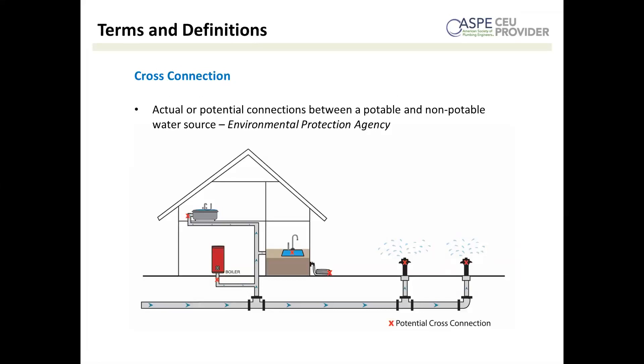A cross-connection, as defined by the EPA, is any actual or potential connection between the public water supply and a source of contamination or pollution. These cross-connections can jeopardize the cleanliness and potability of the public water system in a backflow or back siphonage event. An actual connection is a direct connection to a source of contamination — for example, a boiler feed water makeup line connected directly to a hydronic heating system. A potential connection is something like a hose on the outside of the house that could at any time be connected to a pesticide sprayer.